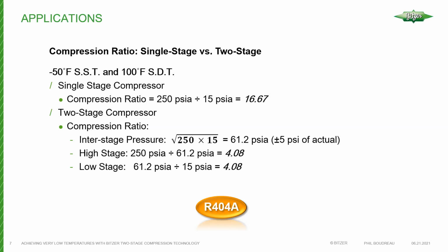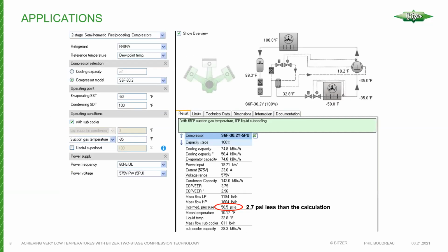This is basically what we're trying to accomplish: equal compression ratios to optimize the performance in each stage as much as possible. Even though the overall compression ratio, if you're reading suction and discharge, is quite high, the individual compression ratios within a two-stage compressor are significantly lower. This results in much greater efficiencies, higher capacity, the whole bit. If we take these operating conditions and place them into the BITZER software, minus 50 and 100 degrees, and it's R404 in this case, we can see that the software reports that the interstage pressure is 58.5 PSIA, which is only 2.7 PSI less than the calculation.